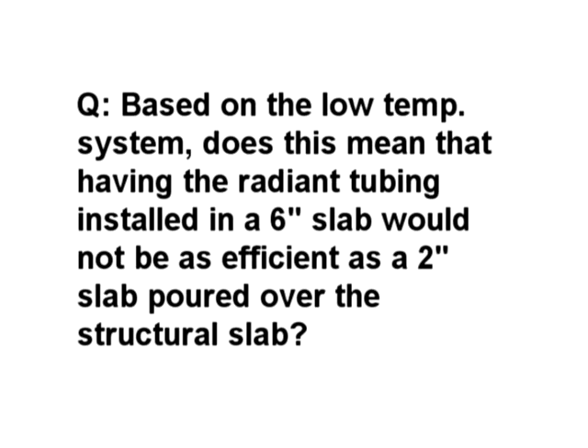John is adding, it's especially important with the cooling. If you're doing slab, that is, yes. Slab cooling we could talk about at length, and it has a bunch of limitations to it. Of course, one of the great limitations with radiant cooling in slabs is trying to switch over between one and the other. That's its great problem. If you're cooling during the day and heating during the night, you're trying to charge and discharge slabs. It becomes a very awkward condition, and that's why radiant ceiling cooling makes a whole lot more sense than floor cooling.